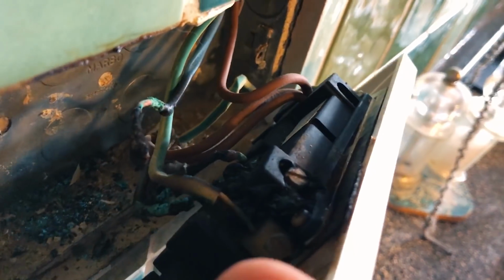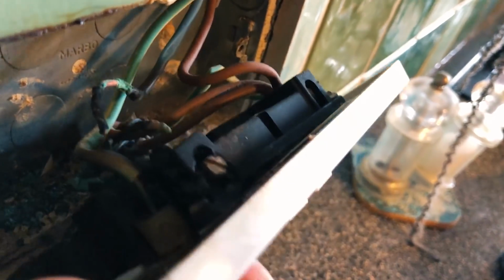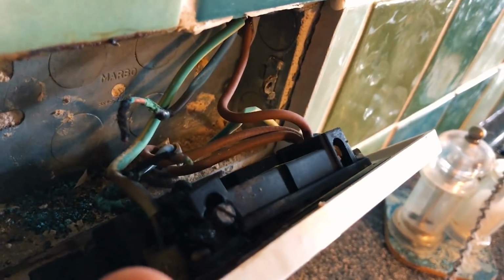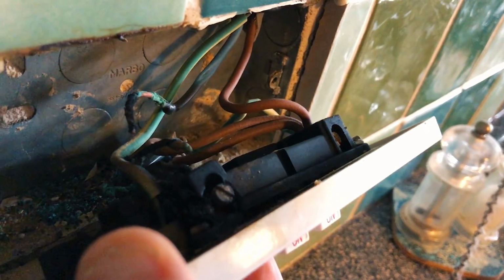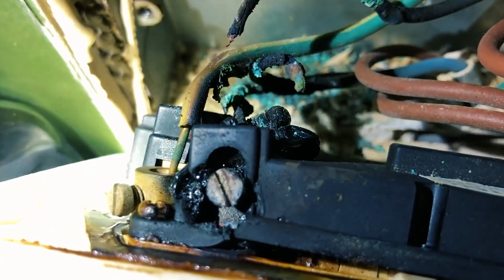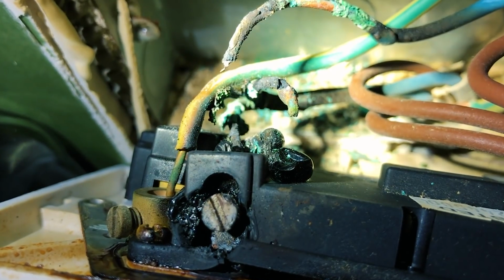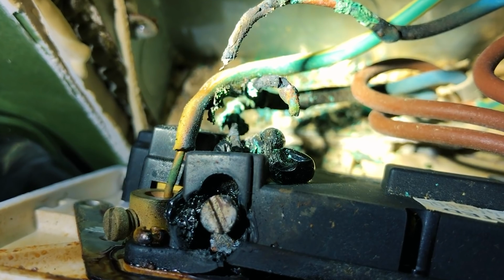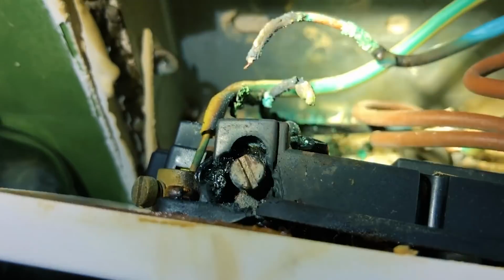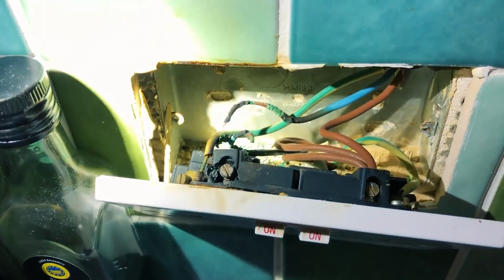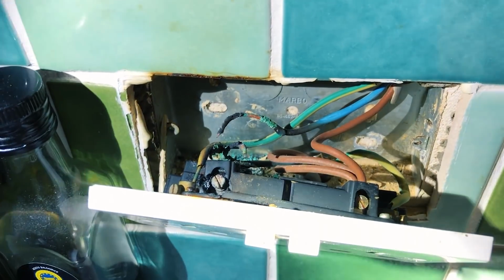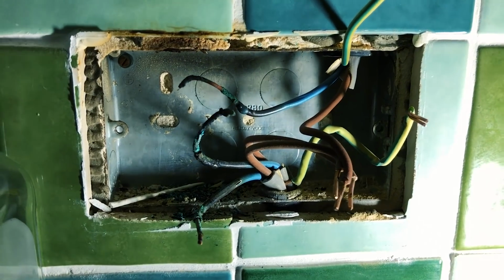So, loose connection maybe. Probably what's happened is there was a loose connection in the back of this socket, and then it's arced and overheated to the point where one or two of the neutrals pulled out, and a lot of the load went down half the circuit, which overloaded it, causing the wires to get even hotter. That caused all this overheating and burning, and that's why the circuit was only working intermittently, because the connection on the neutral was just so loose.